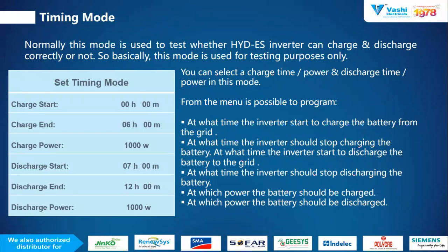You can select a charge time, power, and discharge time and power in this mode. From the menu, it is possible to program at what time the inverter starts to charge the battery from the grid, at which time you have to charge and discharge the battery, and at which time the inverter should stop charging the battery. So it is very much connected with the time of use mode. The time of use mode works in accordance with the timing mode.